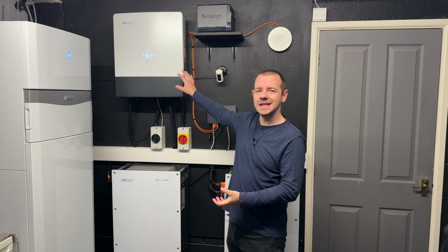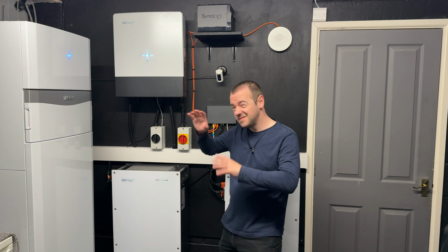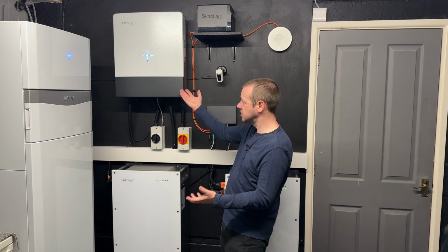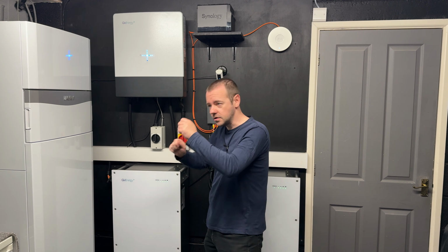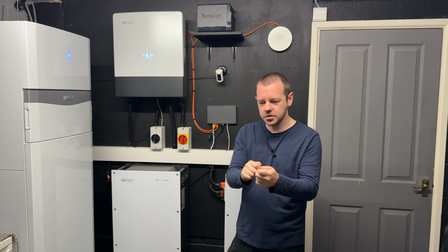Now, these don't really need any maintenance, but a yearly or maybe every 2 years checkup by an electrician or the installer ideally, I don't think it's a bad idea, because a lot of these are high voltage cables going into sockets, and if they're not torqued correctly, which frequently they weren't, I've seen many examples of this, heating up and expansion and contraction, all that sort of stuff, the cables can basically come loose over time. Again, if they weren't torqued correctly, whether it's here or your consumer unit.